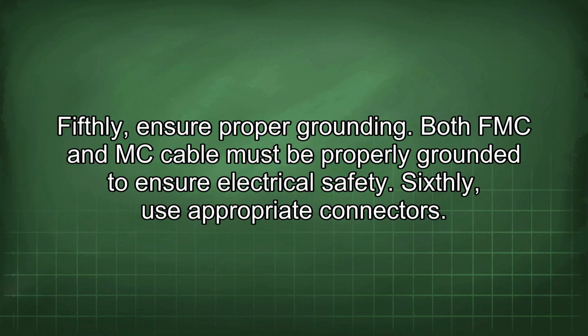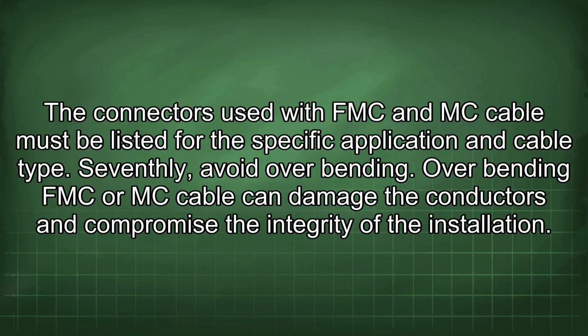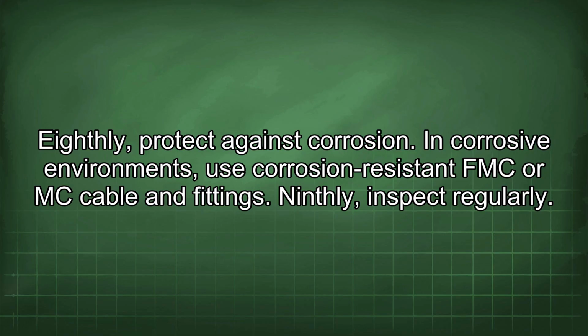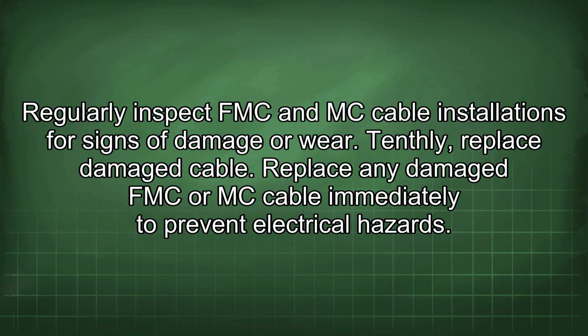Fifthly, ensure proper grounding. Both FMC and MC cable must be properly grounded to ensure electrical safety. Sixthly, use appropriate connectors. The connectors used with FMC and MC cable must be listed for the specific application and cable type. Seventhly, avoid overbending. Overbending FMC or MC cable can damage the conductors and compromise the integrity of the installation. Eighthly, protect against corrosion. In corrosive environments, use corrosion-resistant FMC or MC cable and fittings. Ninthly, inspect regularly. Regularly inspect FMC and MC cable installations for signs of damage or wear. Tenthly, replace damaged cable. Replace any damaged FMC or MC cable immediately to prevent electrical hazards.